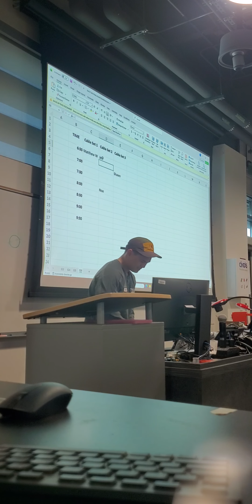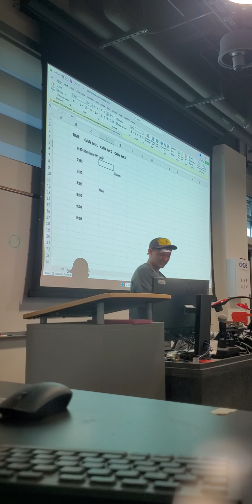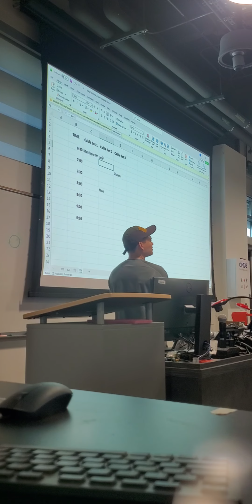Very cool. Freddie, what did you learn in this class? I learned that when you're cutting back the insulation to get a testing, any nick with the blade could cause a significant reading in the cable, so you always want to be sure that when you strip it back, you don't overcut the insulation. Excellent. Yeah, that's a really good tip.